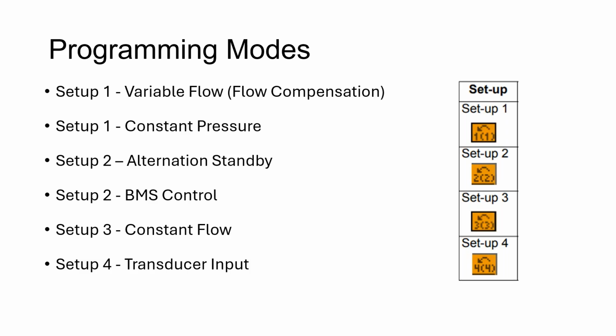At the factory, we actually test the pump with the drive in one of our test loops and map all of the over 100 different points. We use speed changes and flow and head changes and put in a bunch of curves or points into the drive. So all of that information is already in the drive, and that drive goes out with that pump. So just keep that in mind. And there's no after the fact with different parts. So I'm not sure if we answered that question, but I can't emphasize enough that the pump and drive leave the factory together because all of the programming's in there.